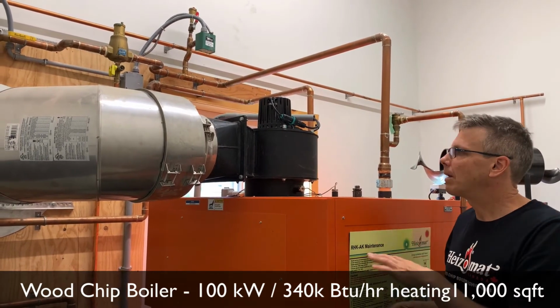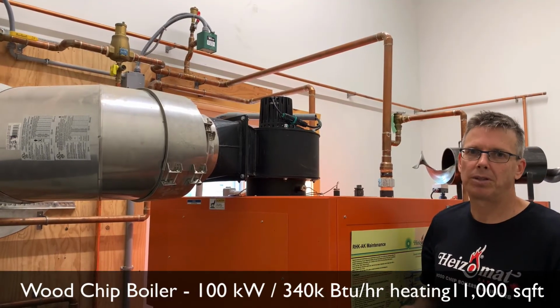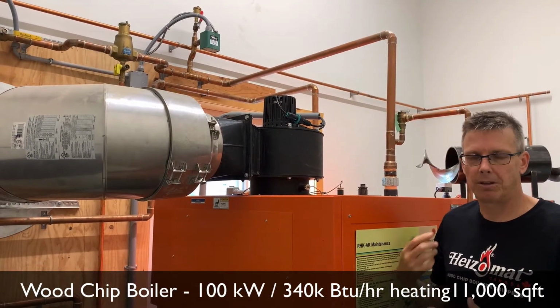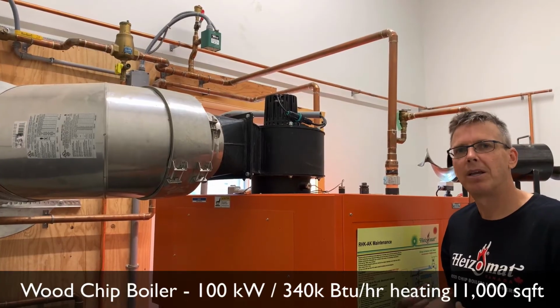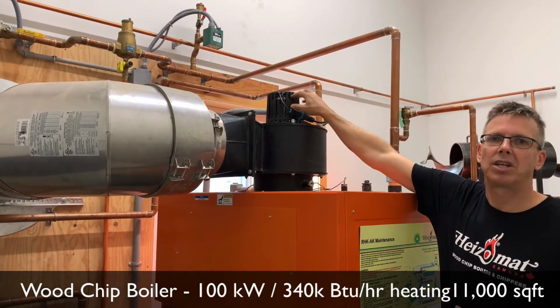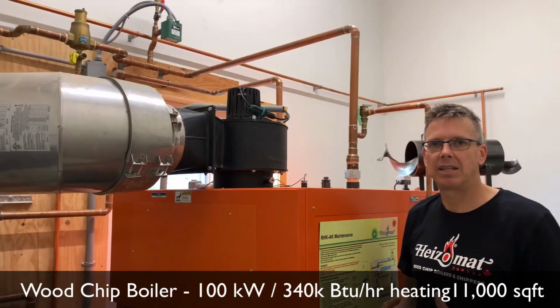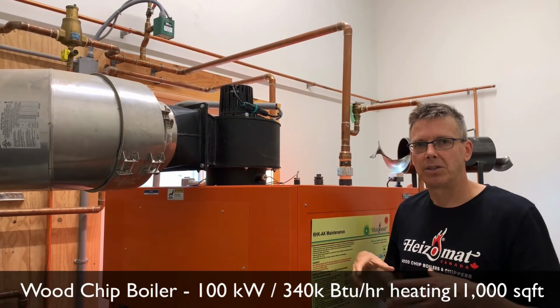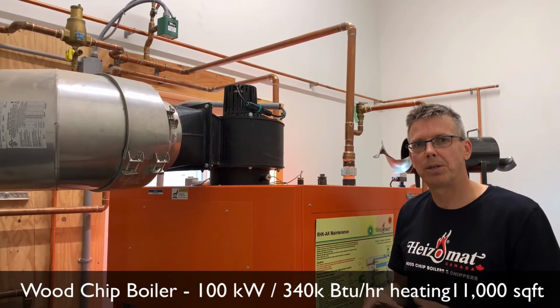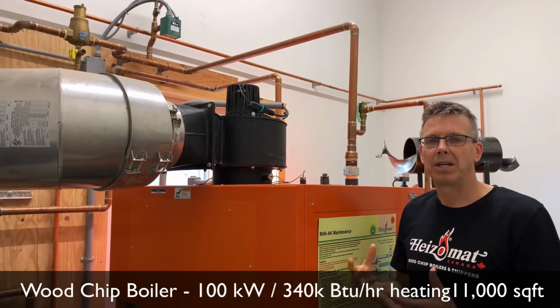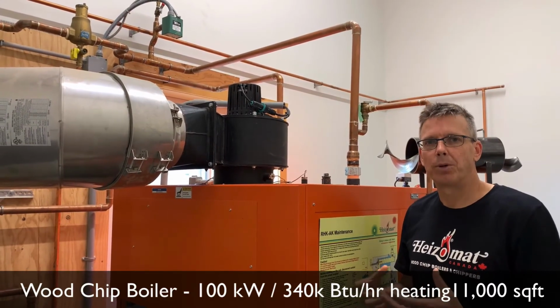So we have an under pressure monitoring system on the boiler, so we're always measuring the pressure inside the boiler. And what the flue gas blower does is it adjusts to make sure that we always maintain that negative pressure within the boiler, considering that we're supplying air into a boiler. It's all about balancing that to make sure that we keep the boiler safe and working optimally.